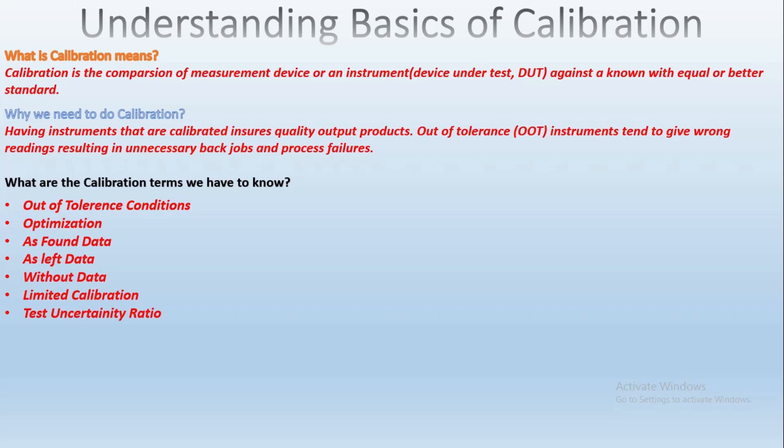The next term is TUR — Test Uncertainty Ratio. This is the ratio of the accuracy of the instrument under test compared to the accuracy of the reference standard.